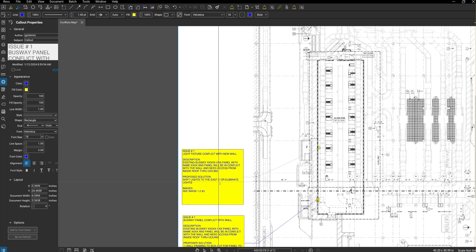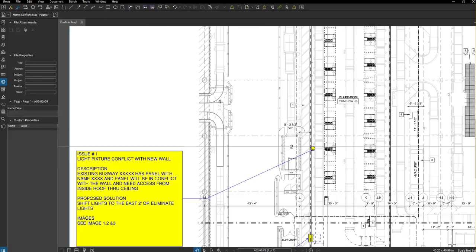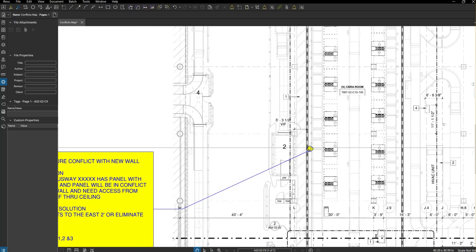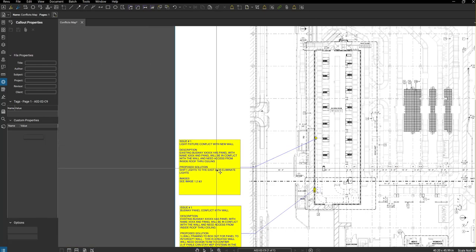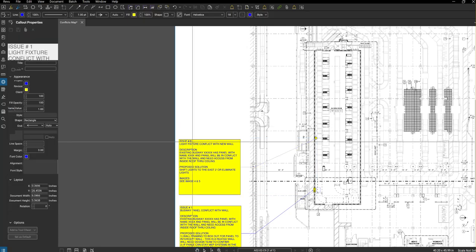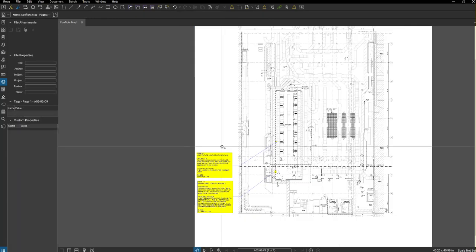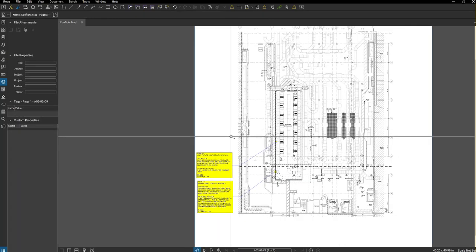And look, one thing you got to check is go to the demo drawings and see maybe these lights are already called out to be demoed and it may not be a conflict. You got to check that, right? So that's image 4 and 5. Okay, and I got to cut it off, and then you change this to issue number 2. And then you can just shrink the box, right? If you don't need the extra room, don't make them extra big, shrink it and kind of move it along. So now you kind of have a little Bible of all these little issues that you have, right?